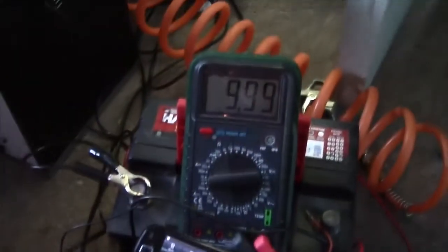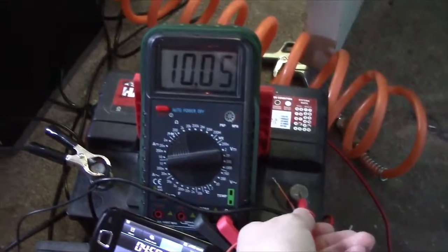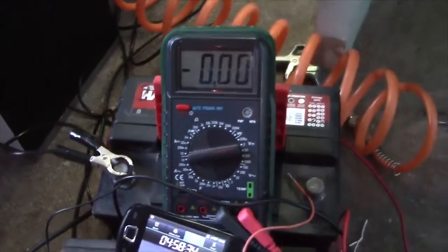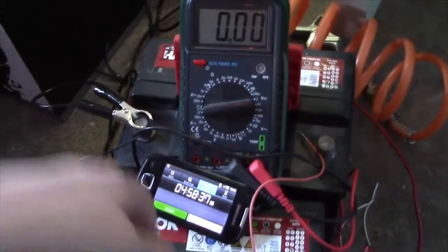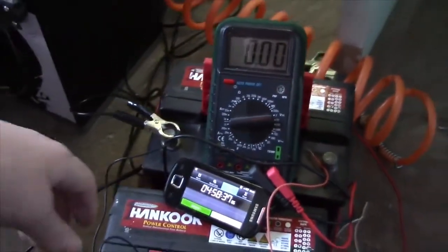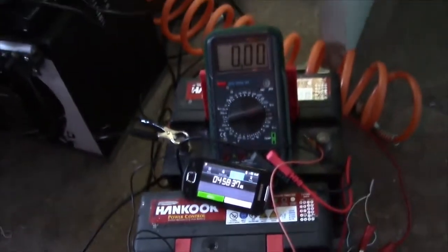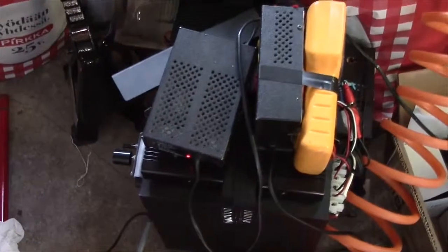Load off and let's see what OCV we get. 999, 10 volts, 10.05. Pretty much exactly the same as before, but at least they've been exercised a bit. So I'm gonna charge them back up and then hook them back up to my UPS and see if they perform any better than last time. And there we go, I'm using two chargers this time to speed the process up a bit.